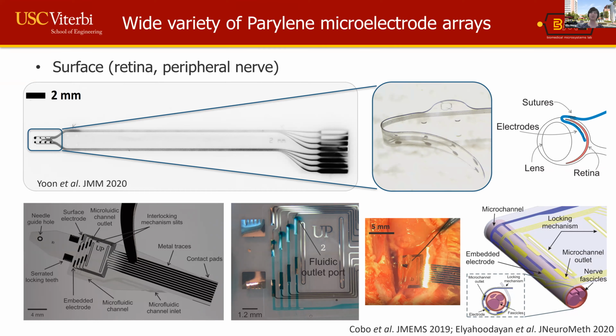fibers for recording. And so here the approach was actually to integrate some microfluidics into the electrode devices. And the purpose of this is actually twofold. One, we want to infuse at very focal sites on the nerve collagenase, a lysing agent, to actually remove some of that collagen content and the protective coating, and then subsequently follow that up with another dose of a growth factor. And that will allow, we hope, for processes that are exposed to grow out into the channels within our device and get closer to the embedded electrodes contained there. So this overall device was designed for that purpose.